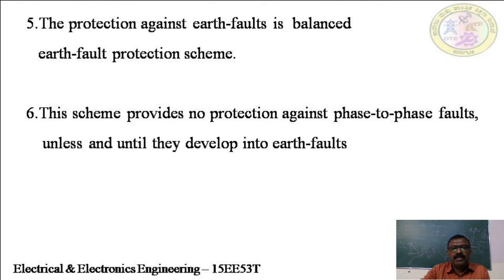This scheme provides no protection against phase to phase faults unless and until they develop into earth faults. See, the drawback in this case is, whereas a differential protection can provide protection against both earth fault and phase to phase fault, the balanced earth fault protection fails to provide protection against phase to phase faults until the phase to phase fault develops into an earth fault.